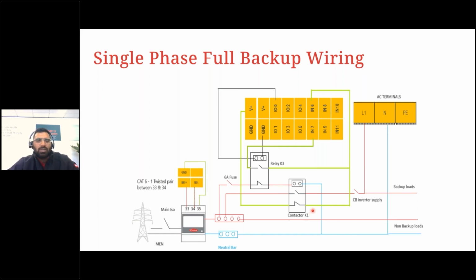To do this, we need some sort of feedback from the contactor and relay to the inverter to tell it, okay, inverter, I have worked, you are okay to work in backup. For this, we use the 12 volt coming from V+. This V+ terminal is always giving out 12 volt, whether it's grid connected mode or backup mode. So what we are doing here is we take this 12 volt, connect it straight to the normally closed contact of the contactor, and then run it straight to IN6, which is the feedback for the contactor. In a blackout scenario, we don't have any power supply coming to this contactor, so this normally closed will remain closed. So this 12 volt is able to pass through this normally closed and come back at IN6. Now the inverter is like, okay, good, I have feedback from the contactor, so the contactor has worked. And it's now waiting for feedback from the relay.